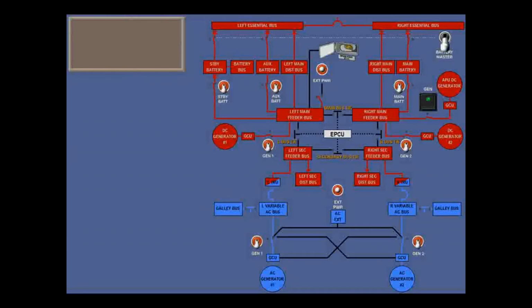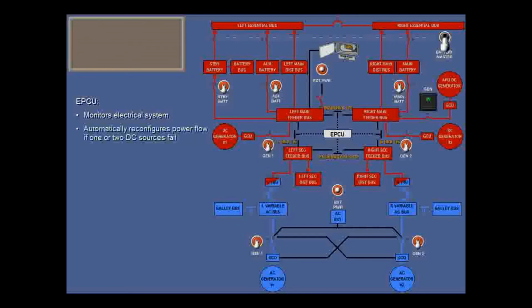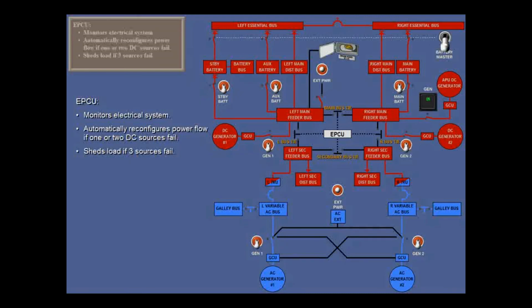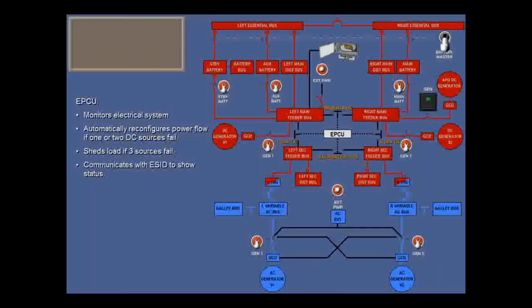Control of the DC bus ties is largely automatic via the Electrical Power Control Unit, EPCU. The EPCU monitors the DC electrical system and contains logic that automatically reconfigures the power flow in the event of a failure in one or two of the four power sources, 2 DC generators and 2 TRUs. If 3 power sources fail, the EPCU provides automatic load shedding. It also communicates with the engine and system integrated display to display the status of the electrical system, and with the crew alerting system to trigger warnings and cautions.